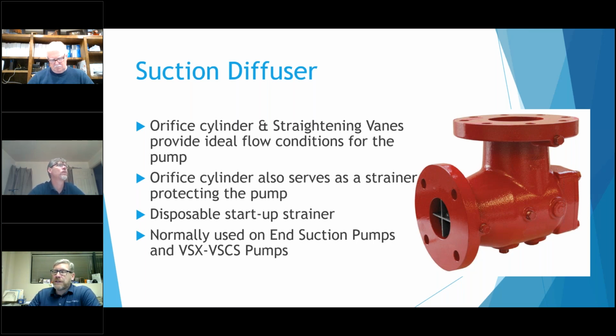You can also use it on some of the double suction pumps. There are certain applications where you need to use it. I'm sorry, it's when the water is coming in parallel with the pump shaft. You can have a lot of problems if you don't use a suction diffuser. Most of the time the water is coming from the top, so you have enough straight flow coming in that you may or may not need one. But people do still use them because it's such a small compact elbow versus a long radius elbow that you would have to use. A lot of people still use them where you have the side suction to the pump, just to make the installation look pretty clean.